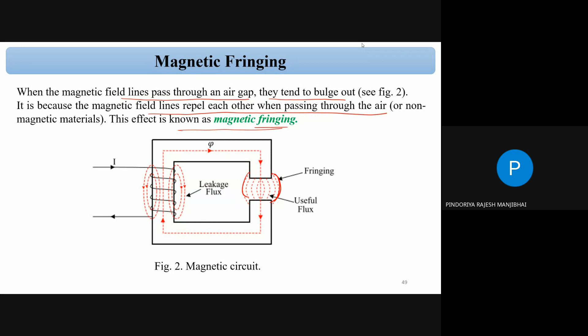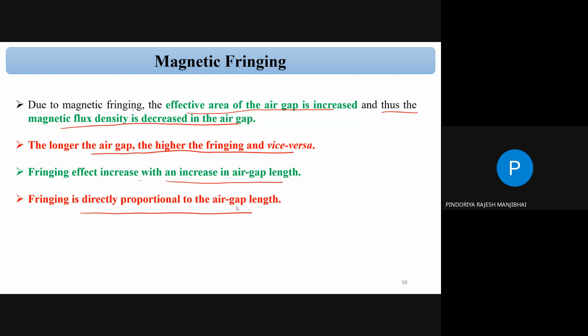Suppose the magnetic fringing effect is there, then what is happening? Due to the magnetic fringing, the effective area of the air gap is increased, which ultimately reduces the efficiency, and thus the magnetic flux density in the air gap is decreased. Yes, the effective area is increased, so the flux density is decreased. The longer the air gap, the higher the fringing, and vice versa. Fringing effect increases with the air gap length. Fringing is directly proportional to the air gap length. So suppose the air gap is high, then the fringing effect is high.